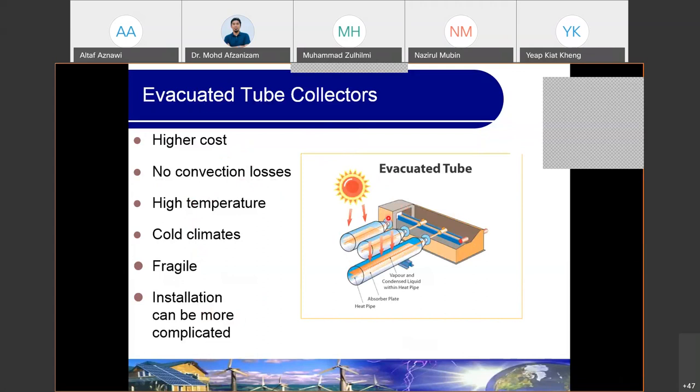Okay. So this is how it looks related to the tube of the evacuated tube. It's quite expensive. Maybe this only one single tube may cost you approximately 1,000 ringgit only for this one tube. It depends on the quality. But it's quite fragile because it's made from glass. So you need to install this kind of collector in a stable area. Because some researchers or users might install it just side by side with the road, where heavy trucks and the vibration will be continuously experienced by the evacuated tube, and yet the glass will break. Okay, so just need to consider the fragile issue.